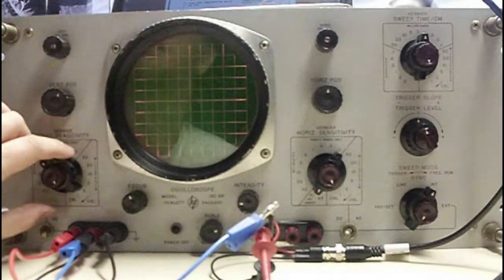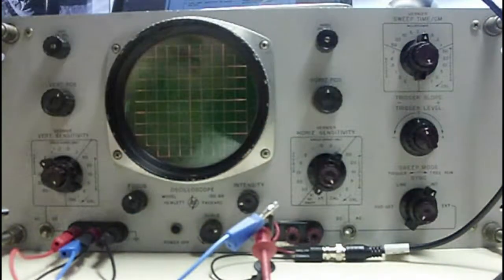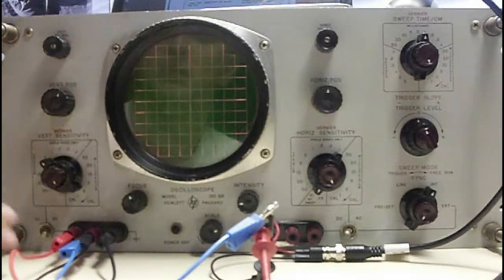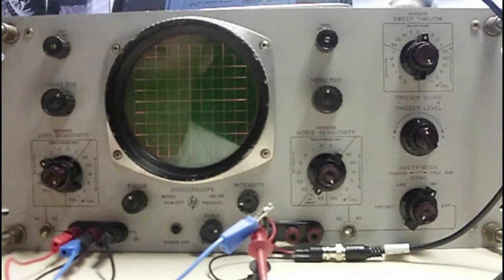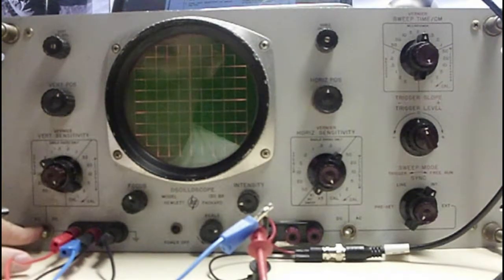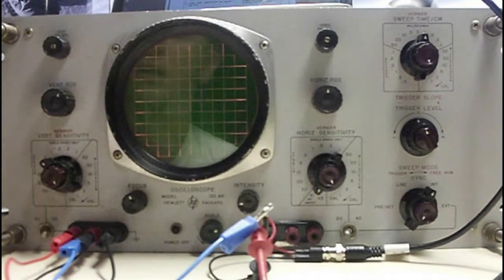Let's see. It says we've already set our sweep mode to preset. And then connect vertical input signal into vertical input. Okay, so we've done that. We've connected here. Set AC/DC switch to desired coupling. I want DC coupling. Then set vertical sensitivity to the desired level, so I set that to 2 volts per division. We still have the horizontal set up for the internal sweep triggering. I just did step 6, set vertical sensitivity.